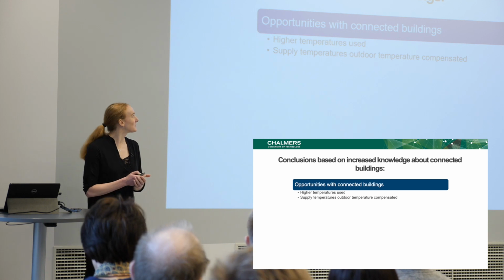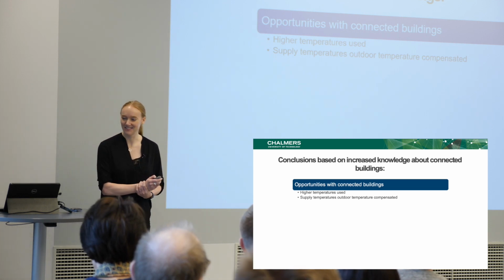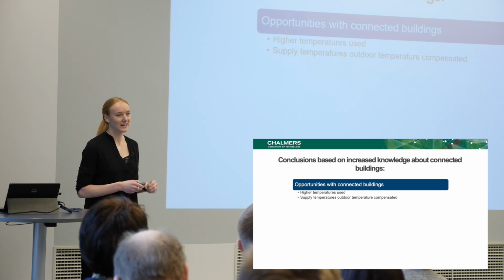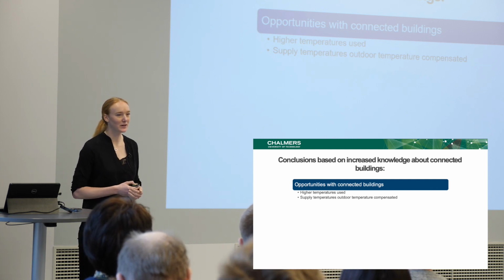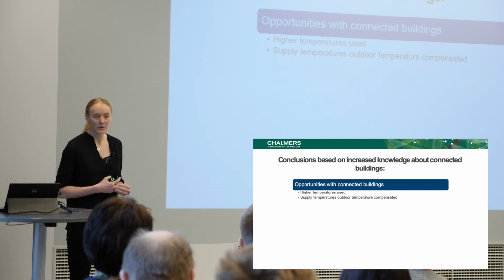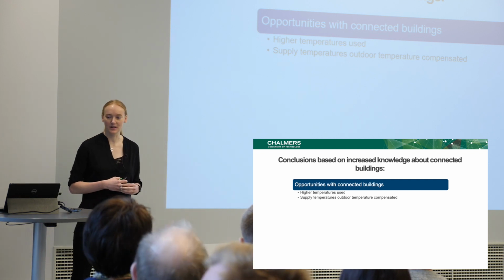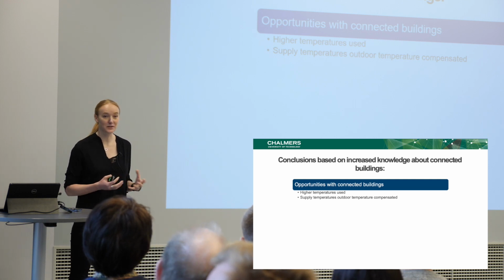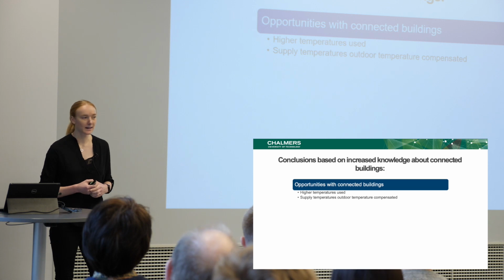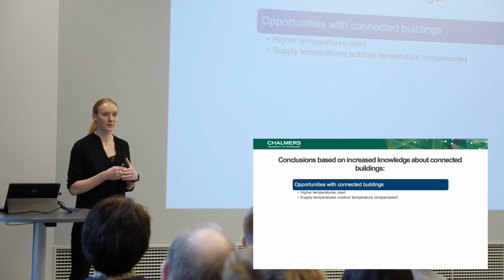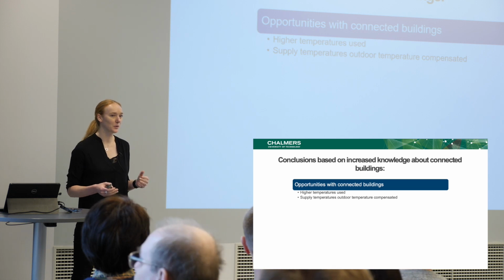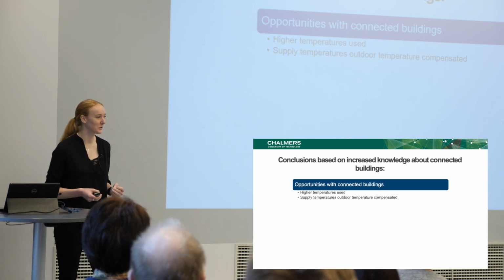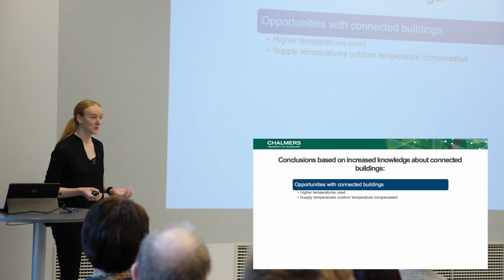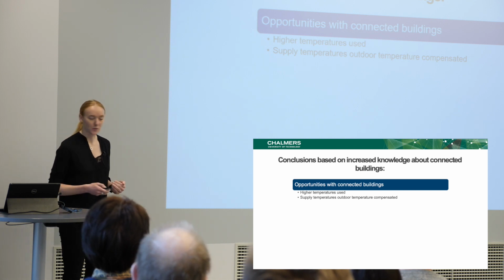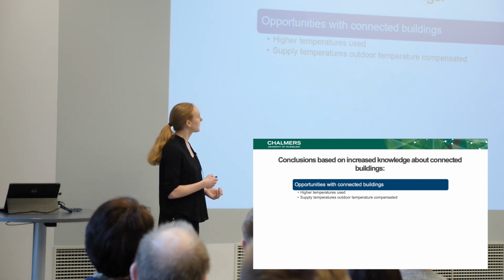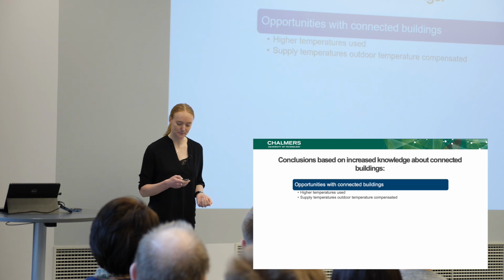So with that, I'm going to try and summarize everything. Based on the increased knowledge of the customer connections and their buildings, we now know that there are some opportunities, such as buildings that already use higher temperatures than 80 degrees. And also the fact that they don't use the same temperature throughout the whole year. So when the temperature outside is lower, the outdoor temperature compensates the supply temperature, and it's higher. So that's what this means here. The supply temperatures are outdoor temperature compensated in many buildings.